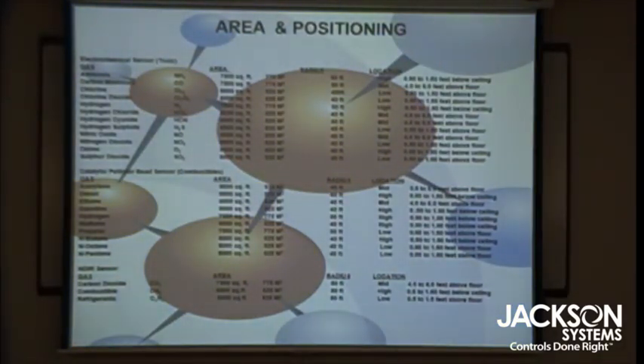So what do you really do for a parking garage where they're concerned about diesel cars and trucks? Place them close to the floor, if it's just for cars and trucks. Because normally you have a height limitation. Most of the exhaust stacks going to the ceiling are for big trucks, you know. The majority have exhaust close to the floor, so we place it 12 to 18 inches off the floor, at the height of where your exhaust would be. So because the exhaust gas, of course, is warm, it's not going to rise that much, but it's eventually going to stay closer to the bottom. And that's where you'll pick the NO2. The exception to the rule is buses and those dump trucks where they have exhaust to the top.